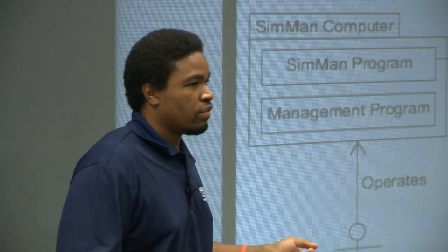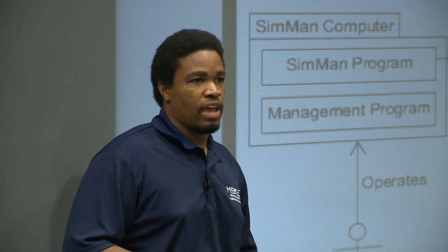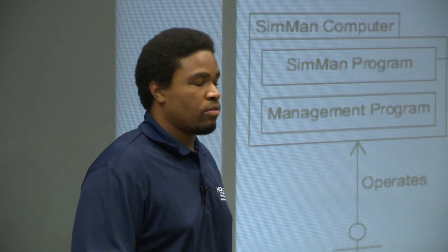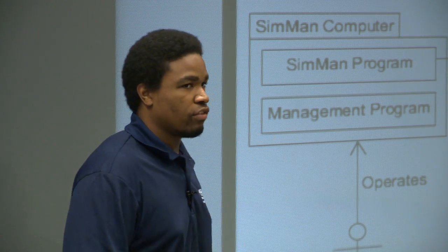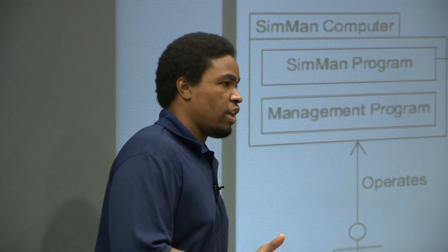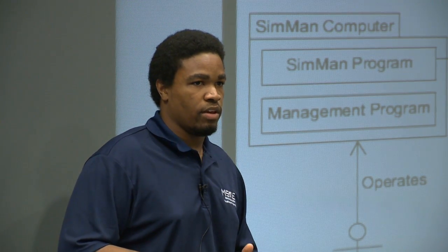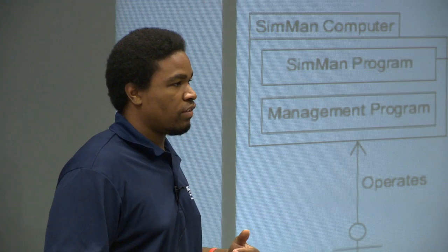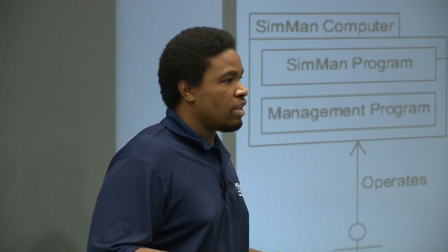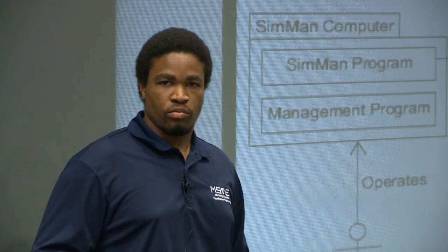But the technician is still there to make any changes that need to happen with the Simman program, and to make sure it's capable of monitoring all the actions that are occurring in the system. There is a management program that routes all messages sent by the IV pump and the patient monitor that allows the technician to see everything that's going on in the system, even though it may not be as involved as it was previously.